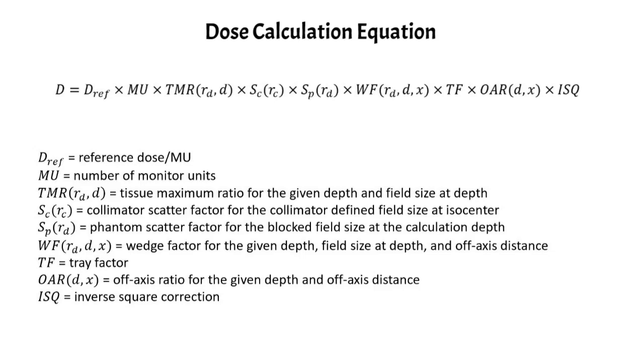SCRC is your collimator scatter factor defined at the isocenter. SP is your phantom scatter factor for the blocked field size defined at the depth of calculation. You have your wedge factor, which is a function of the given depth.